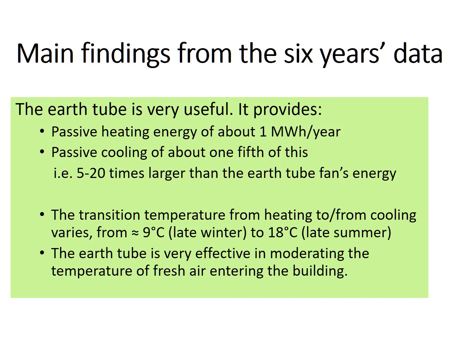So those are the main findings. Passive heating, about 1 megawatt hour per year. Passive cooling, a fifth of this, much larger than the energy used by the fan. The transition temperature varies from 9 to 18 over the year, and it's very effective in moderating temperature of fresh air entering the building.